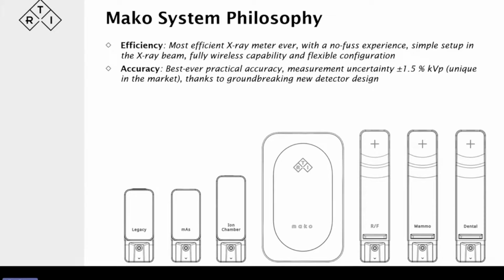Accuracy is, of course, also important. We're aiming for the best ever practical accuracy when it comes to measurements. And the uncertainty that we've experienced and we're looking for is 1.5% of the kVp, which is unique in the market as far as we've seen. And that again is thanks to the new detector design and the algorithms that process the data received from the detector.